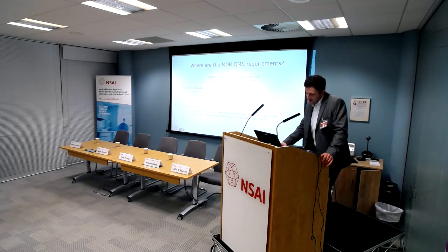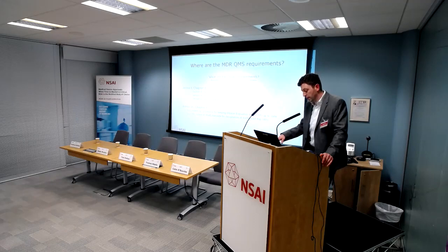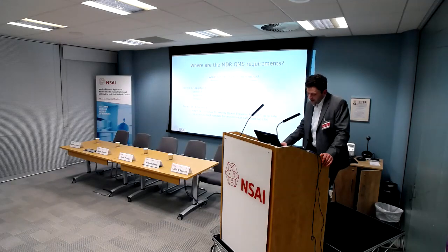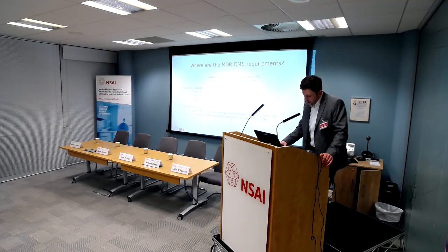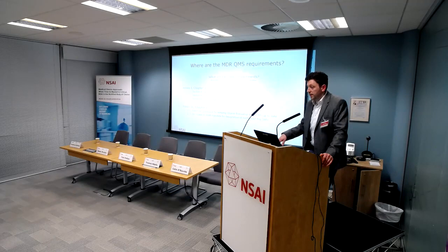Again, this list does not cover all the requirements, it covers some of them. So Annex 1, Chapter 1, again, it's all risk management. From 13485, it'll follow right through to your MDR. And then Annex 9, Chapter 1, this is your clinical evaluation plan. It's slightly different to your clinical evaluation report. Both are needed, but the plan needs to be kept up to date continually. And then 2.2 Part B, and 4, the draft mandate for the designation of the authorised rep. Colin talked about this earlier. It's important to know, particularly with the Brexit side of things, where or when you need to appoint that.